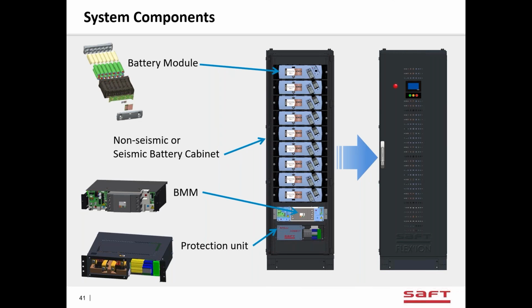For 120 volt systems, we need 5 of those modules, the blue modules. In production, they're actually black, but in this picture, they're blue. We need 5 modules, plus the BMM and the protection unit, as those are parts of our battery management system. And then on the first cabinet, we call it the master cabinet, we have an LCD display so that you can get all the battery information displayed and you can know what's going on with the battery.